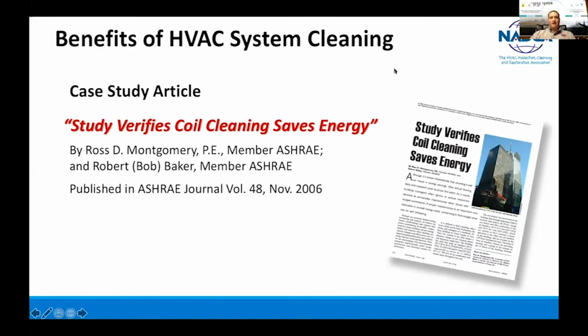The study was that a system is built and put together by an engineer to work within certain parameters. Once the system starts to become fouled or soiled or have lots of contaminants within it, the system doesn't operate within the building envelope in some cases. And so to maintain this, we always make sure we clean the HVAC air handling unit and ductwork as necessary. One of the best things that we ever did was to be able to take the coil and isolate it and actually do a case study, which they did, to show how much money was being saved possibly just by cleaning the coil.